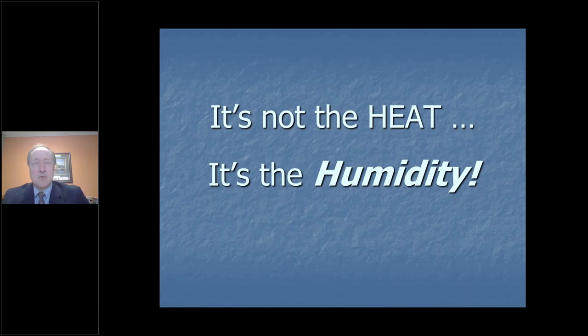Okay. Well, I'm not sure I answered the last one, but if it's okay, let me answer real quick. Let's say it's a chilled water system. Depending on what your chilled water temperature is, if you are having to drive your chiller down to a very cold temperature just to do the dehumidification, then you'll be better off if you put a desiccant dehumidifier in to do the difficult dehumidification, and then you can raise the water temperature of your chiller so that you're not having to run it so cold all the time.